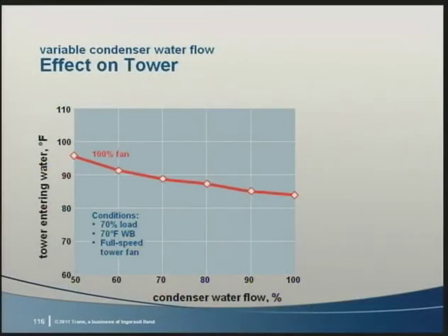Cooling towers can reject heat at many conditions. Shown here is the performance of the cooling tower with a chiller load of 70% and an outdoor air wet bulb temperature of 70 degrees. We've charted the temperature of water entering the cooling tower. On the right side of the chart, we see that the water temperature entering the tower is about 84 degrees at 100% water flow. If we reduce the water flow rate, the temperature entering the tower goes up. Since we're rejecting essentially the same amount of heat with lower water flow, the water temperature entering the tower rises. For example, at 50% flow, it's 96 degrees.